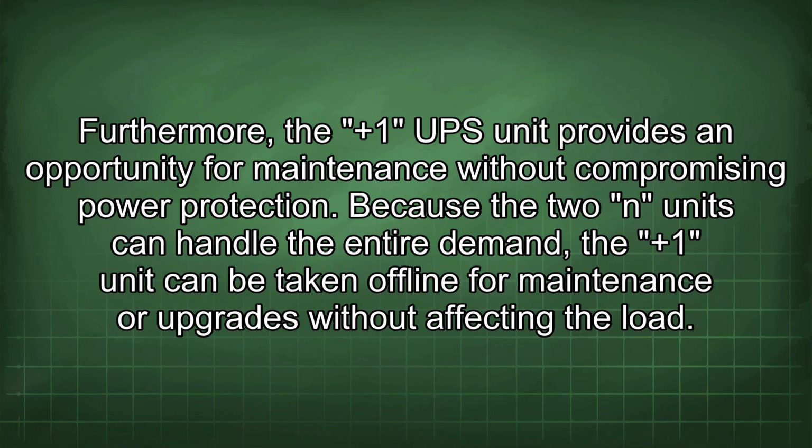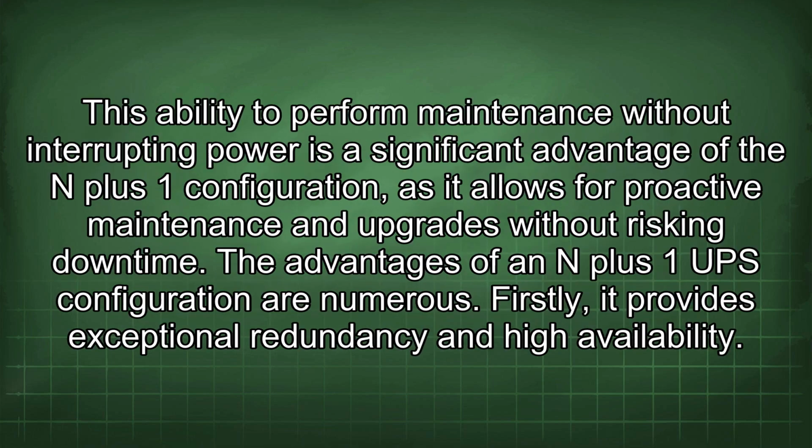Furthermore, the +1 UPS unit provides an opportunity for maintenance without compromising power protection. Because the 2 N units can handle the entire demand, the +1 unit can be taken offline for maintenance or upgrades without affecting the load. This ability to perform maintenance without interrupting power is a significant advantage of the N+1 configuration, as it allows for proactive maintenance and upgrades without risking downtime.